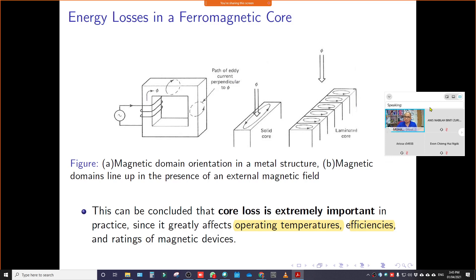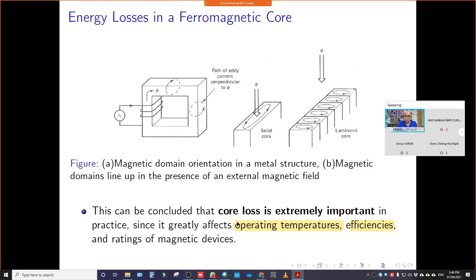Eddy current loss causes the operating temperature to increase — if the loss is high, the equipment gets very hot, which causes even more losses. That is why for large power transformers dealing with 11 kV or more than 200 kV, there is a cooling system — usually using oil — to cool the transformer. Operating temperature is affected by eddy current losses, and these losses also affect the efficiency of transformers and machines.